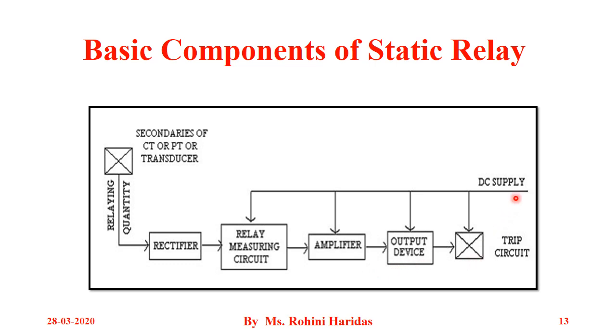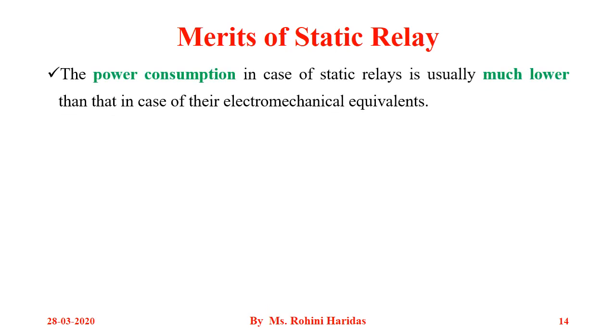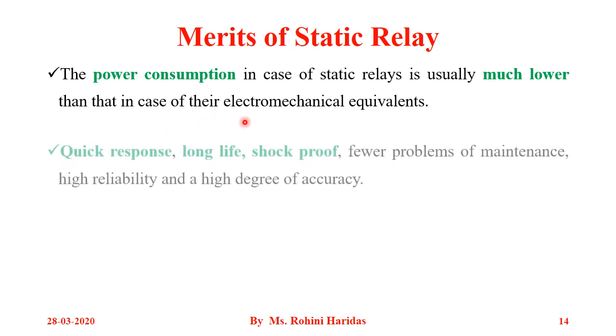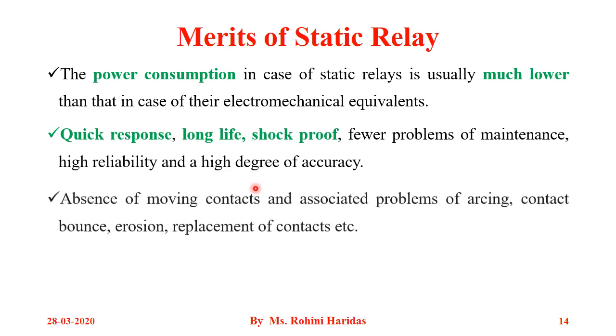Now let us see the merits of the static relay. The power consumption in the case of static relays is usually much lower than in the case of electromechanical equivalents. Other advantages include quick response, long life, shock proof, few problems of maintenance, high reliability, and a high degree of accuracy.